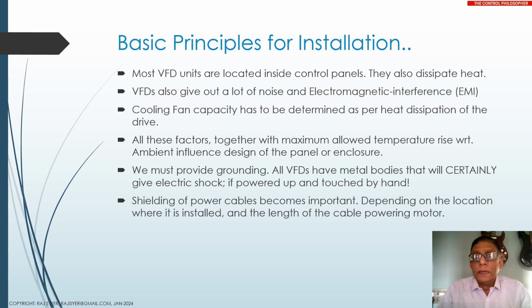Okay. Then we come to the point of grounding. See, grounding or earthing the VFD is very, very important. All VFDs have got solid metal bodies to dissipate the heat. Alright. Now, grounding them, giving them a proper earthing is very, very important. If you run a VFD without earthing, if you touch the body of the VFD, you are going to get a severe shock. Alright. Okay.